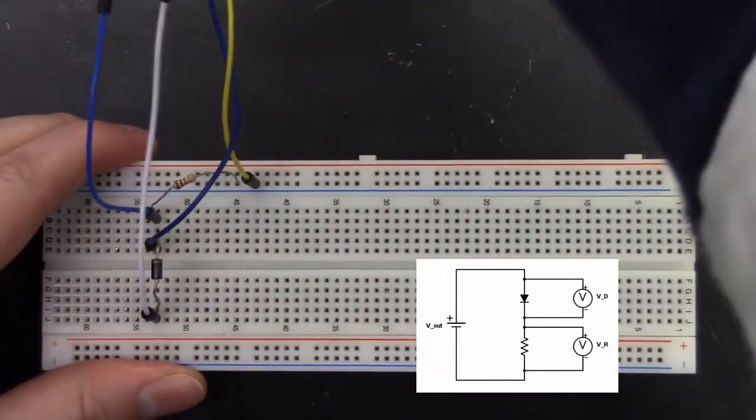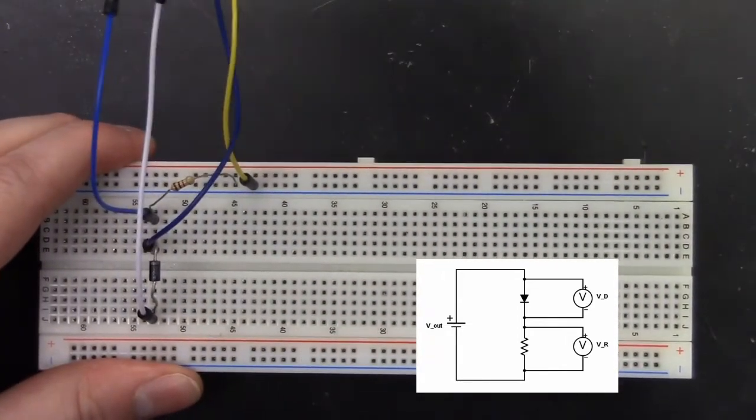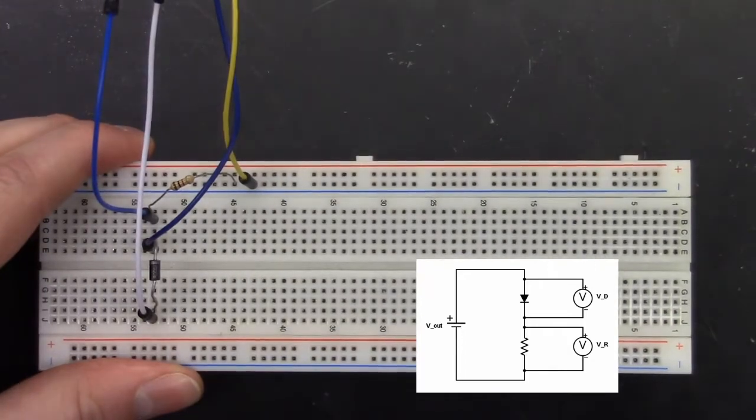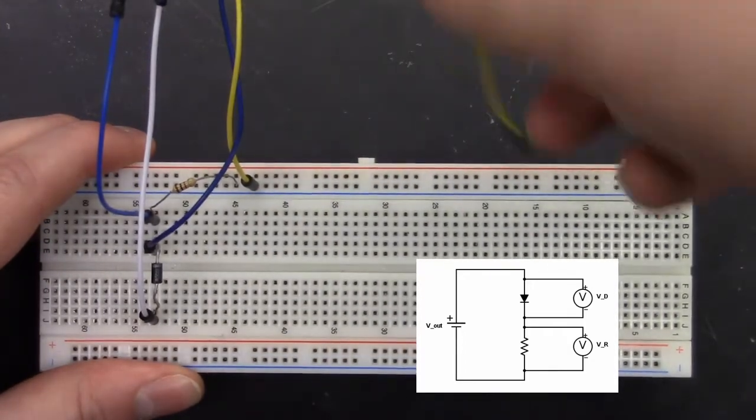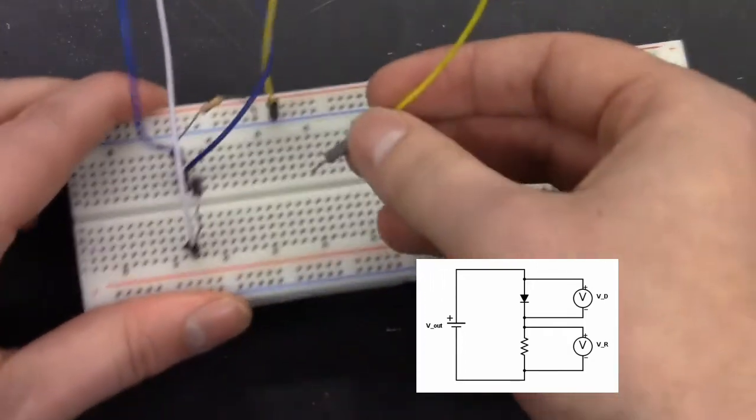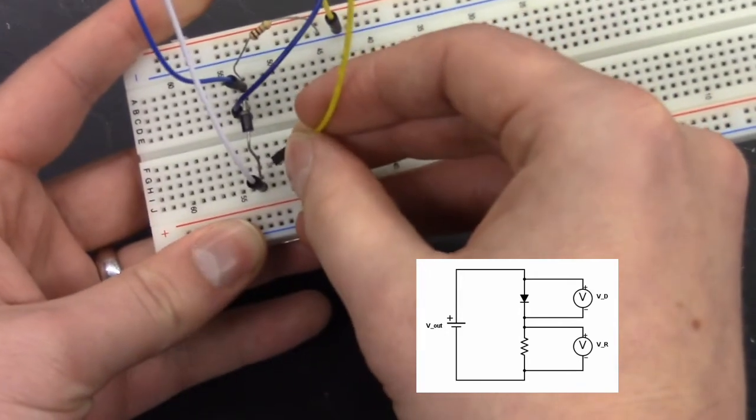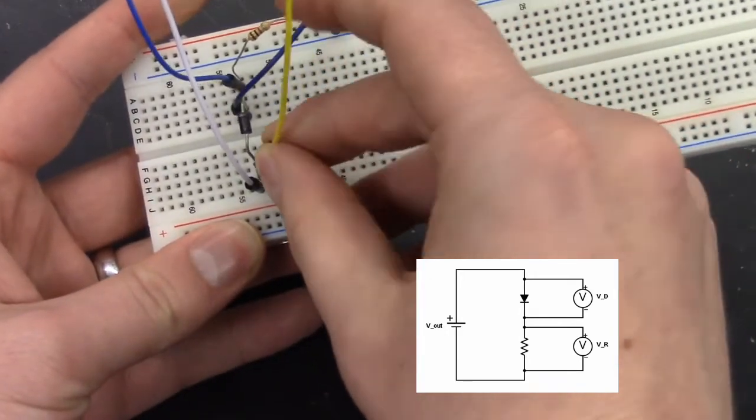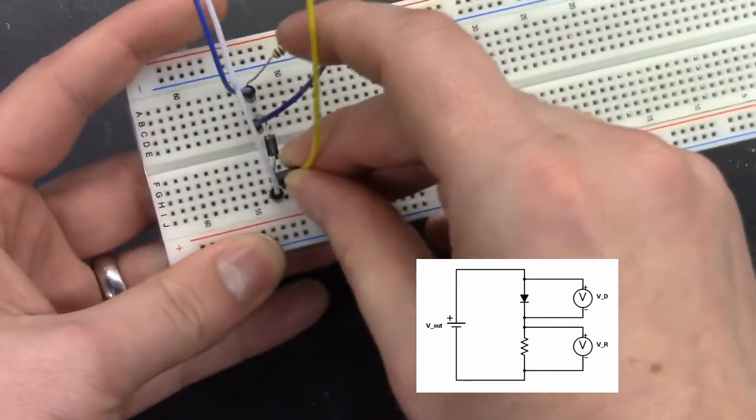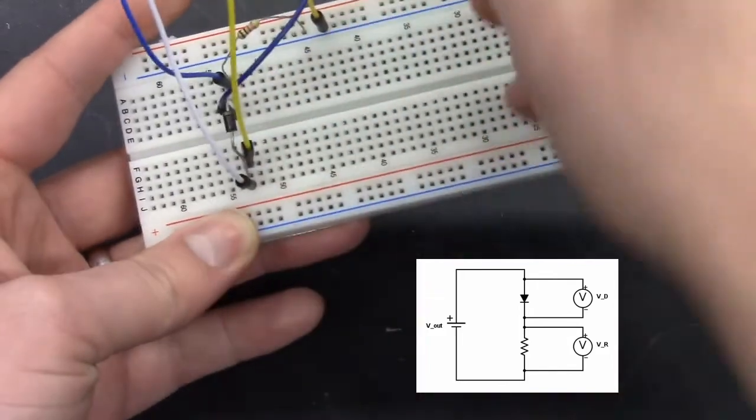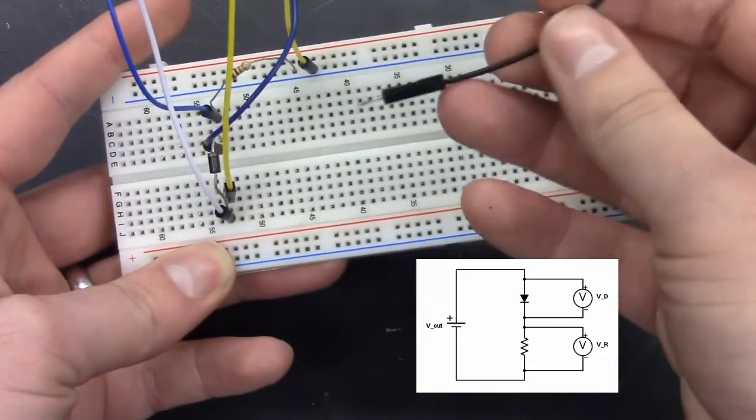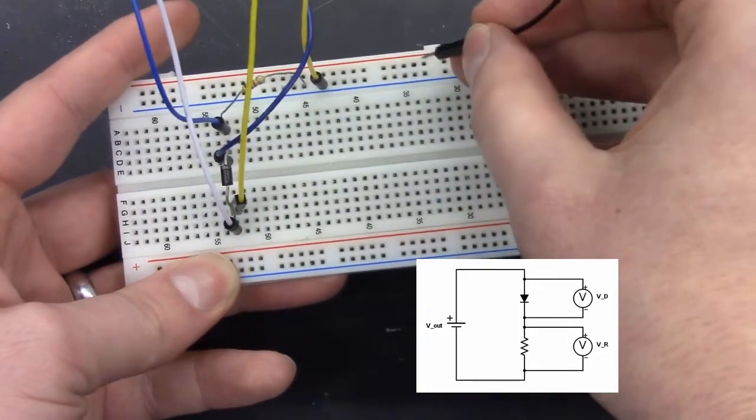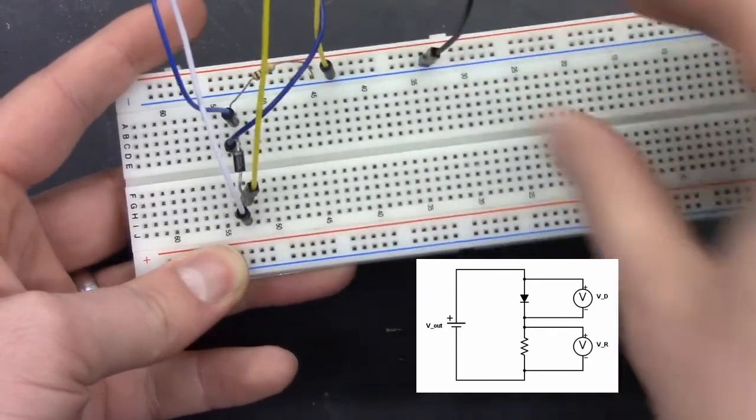And then last is the output voltage of our analog output module. So one wire will be the output voltage signal, which in a forward bias will be positive. And then the second wire will be ground. Put in this column.